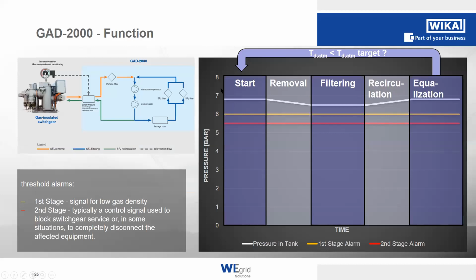Another way to show it is regarding the pressure in your gas compartment. The pressure will drop a bit when we take a certain amount of gas out. Then we are in the filtering phase, and when we are done filtering, we put it back in the recirculation, and we wait a couple of minutes to give the compartment and the gas time to equalize itself again. And the pressure, which relates to the gas density, is always staying above the first trigger and the second stage trigger.